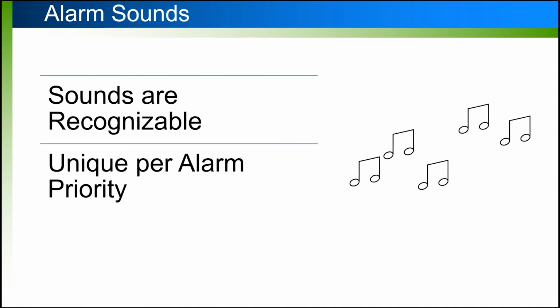So we recommend using unique alarms per priority. If you have high priority alarms, you definitely want to know that was a high priority alarm. If an operator happens to be away from their console and hears a priority 4 alarm come up, they know, hey, I can continue, I can finish what I'm doing. But when they hear that noise for a priority 1 or even a priority 2 alarm, they kind of know, I need to stop what I'm doing, I need to get back to that console and figure out what's going on. So the use of sounds is important, and we should be using different sounds per alarm priority.